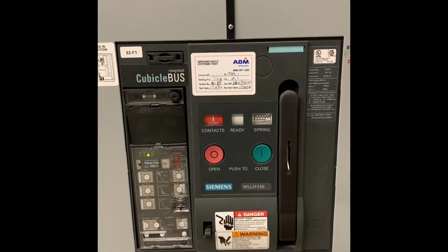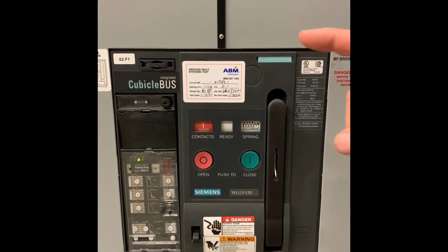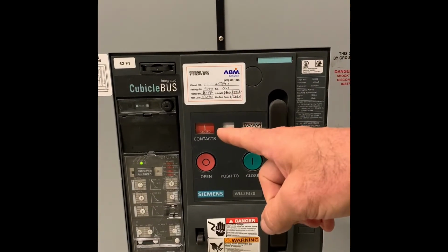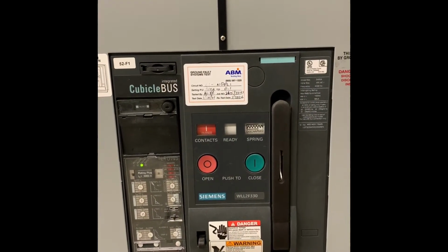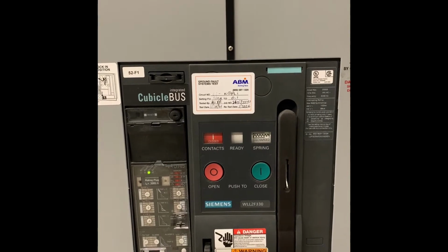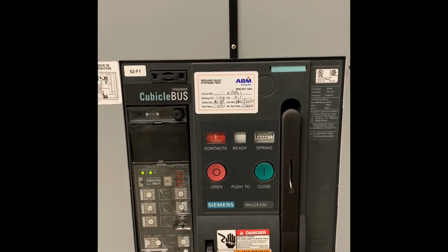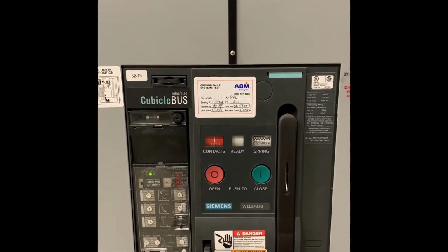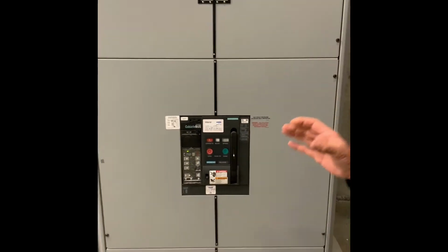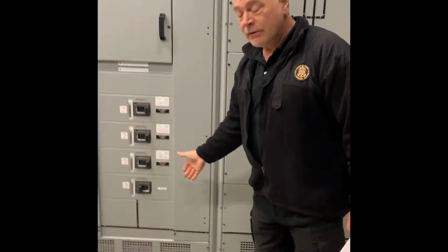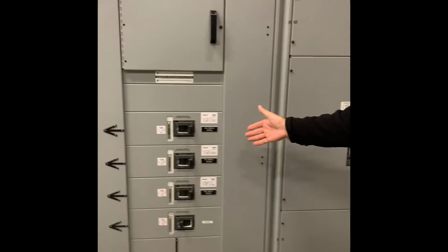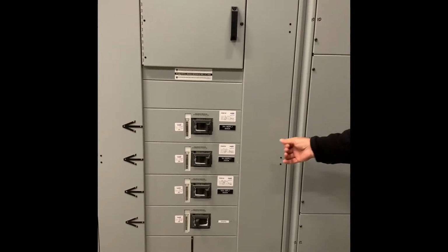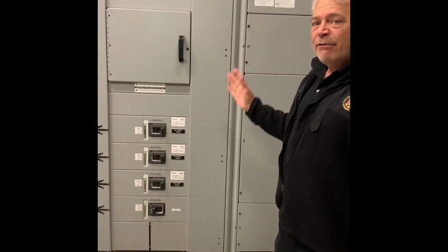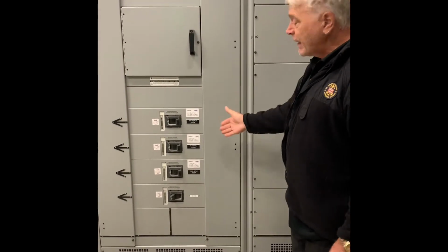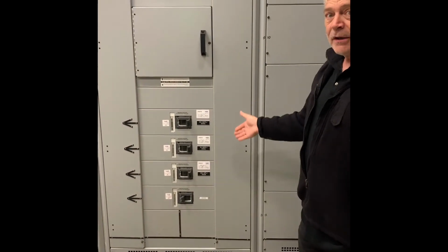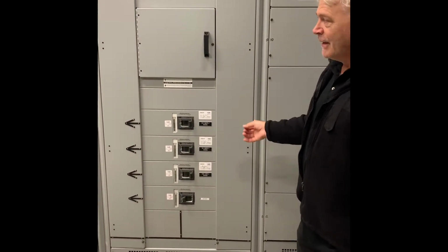If this was tripped, it would show tripped, and you pump the handle until it goes green again. This is only done by authorized personnel after you figure out why it tripped. You cannot just come in and reset the breaker, and that's with any of these breakers. If this breaker tripped, it tripped for a reason. So don't just turn it back on again. Find out what the problem was. This breaker did its job and opened the circuit to protect equipment and life.